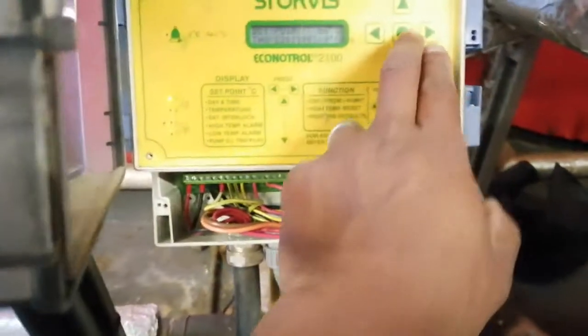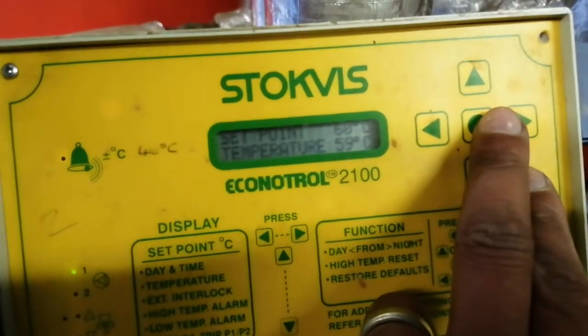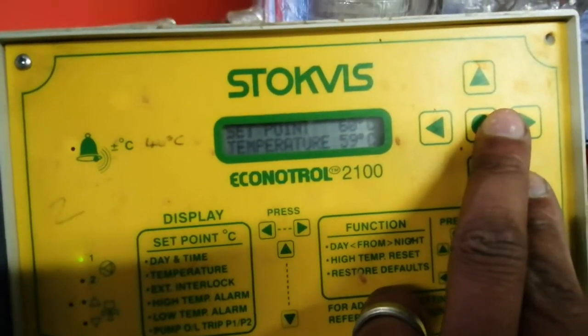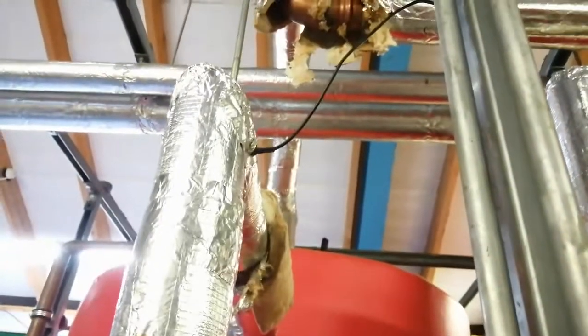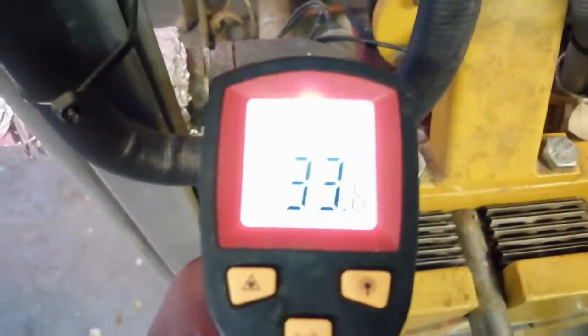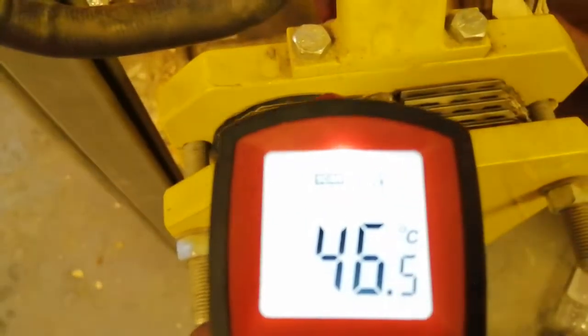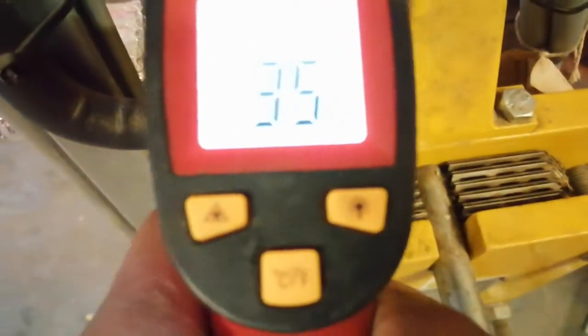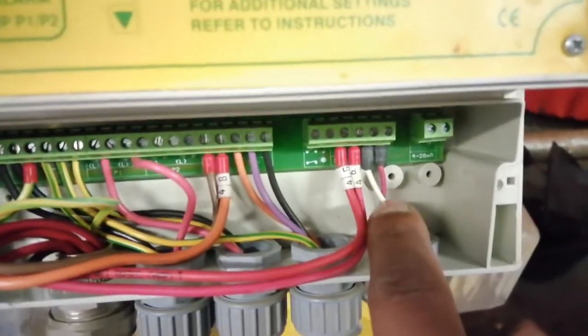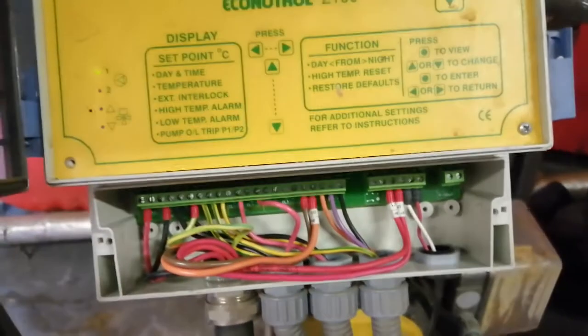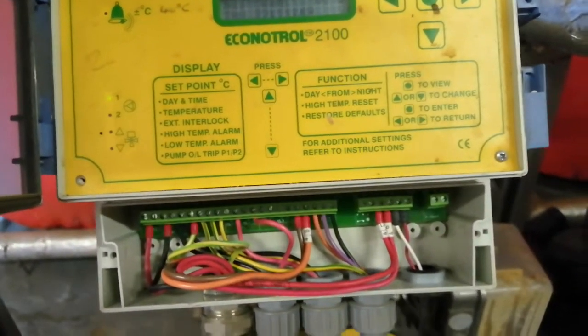I don't believe the temperature sensor is correct on this unit. It's saying 60 Celsius, but as you could see at the control panel earlier, we had no reading at the upper sensor of anything like 60 Celsius. I've also used my laser gun, though it's not pinpoint accurate. Here's the temperature sensor at the back, and the readings I get are nothing like the 60 Celsius that it is stating. I think it's more like 50 Celsius that I'm getting through here. So the temperature sensor here will need changing. There's possibly a resistance test that could be done on that at certain temperatures, and I'll be able to find out if my sensor is accurate. I believe it's about 10 Celsius out.